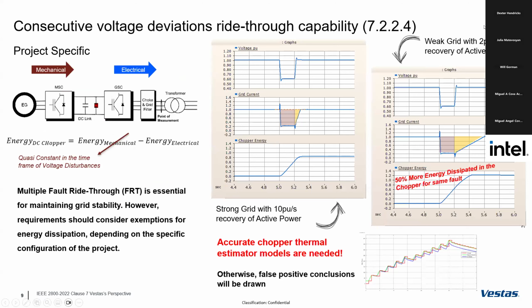One thing that we are seeing in the industry is that some ISOs are suggesting some tests to run in EMT simulation or RMS simulation, doesn't matter, to evaluate this. And we have to keep that in mind when we are doing this, because the reality is that most of the models out there do not contain a proper thermal model for the chopper, or whatever the technology is that dissipates the energy from the resource to the grid. So if you don't have an accurate model of your energy dissipation, you cannot monitor the temperature, which is the weak point when you have multiple FRT.